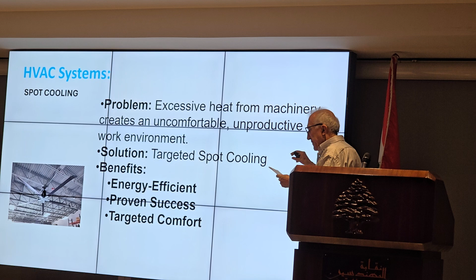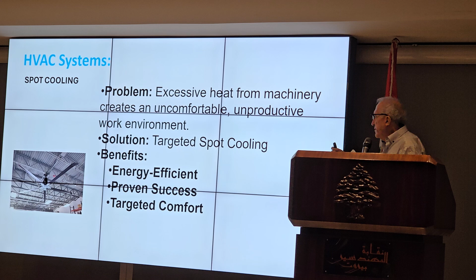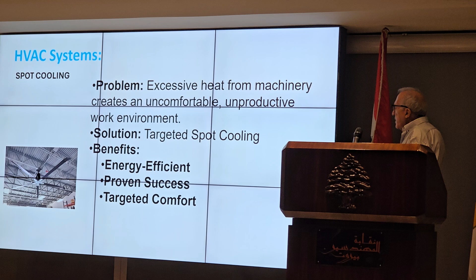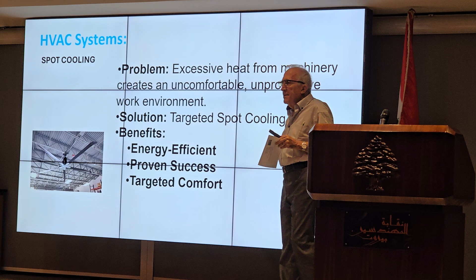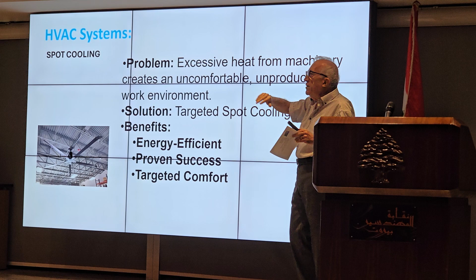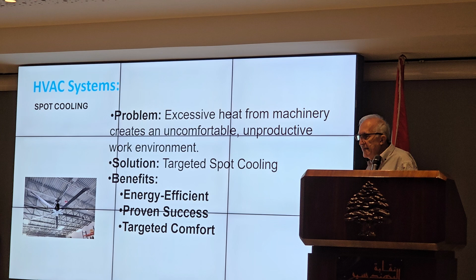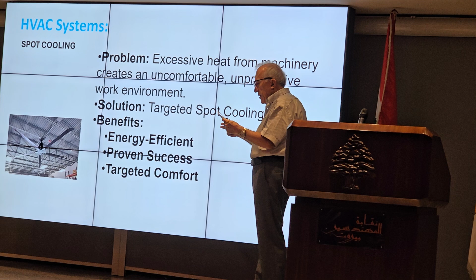and well-being. We utilize high efficiency fan coils that use high temperature water. Instead of using water at 5 degrees, we are using water at 15 degrees, because we want the breeze that is coming on the people to be around 25, 27, not like normal air conditioning where you get the outlet temperature at probably 17. This prevents overcooling, which can lead to health issues like colds or stiffness.